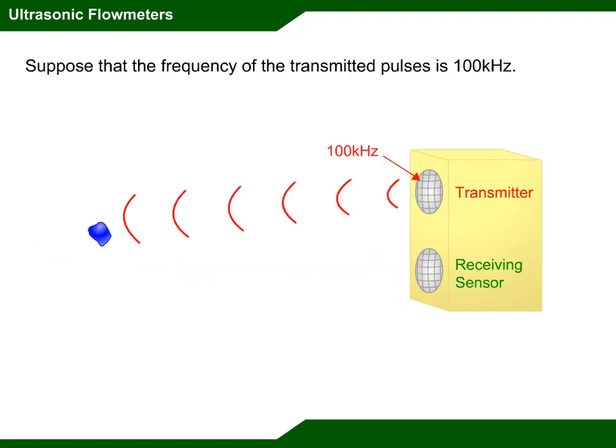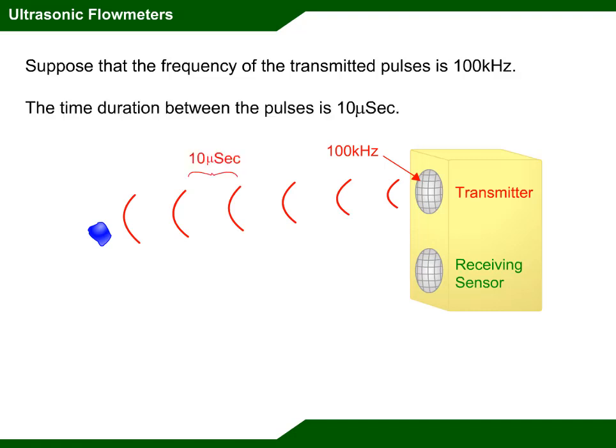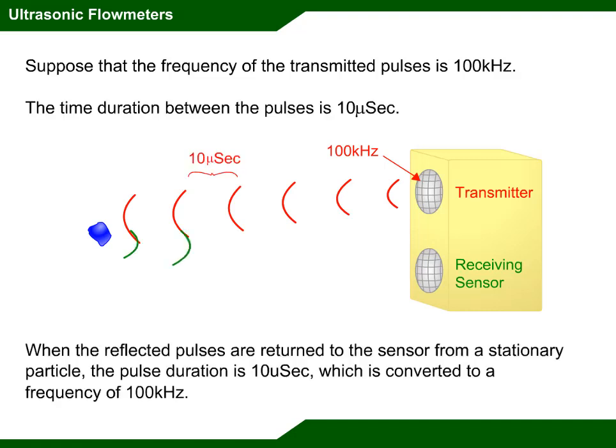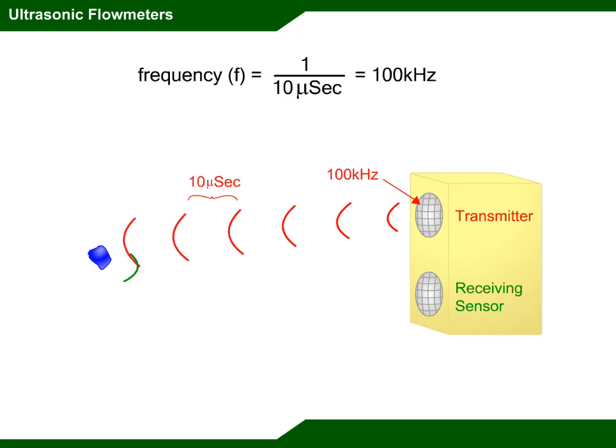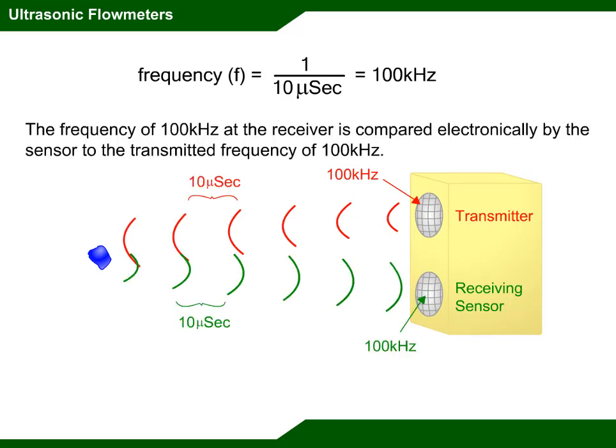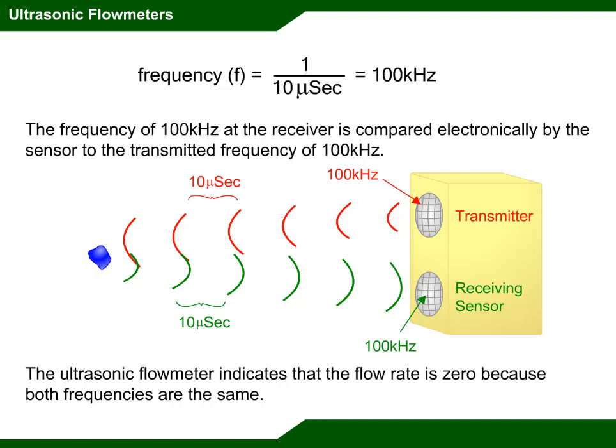Suppose that the frequency of the transmitted pulses is 100 kilohertz. The time duration between the pulses is 10 microseconds. When the reflected pulses are returned to the sensor from a stationary particle, the pulse duration is 10 microseconds, which is converted to a frequency of 100 kilohertz. The frequency of 100 kilohertz at the receiver is compared electronically to the transmitted frequency of 100 kilohertz. The ultrasonic flow meter indicates that the flow rate is zero because both frequencies are the same.